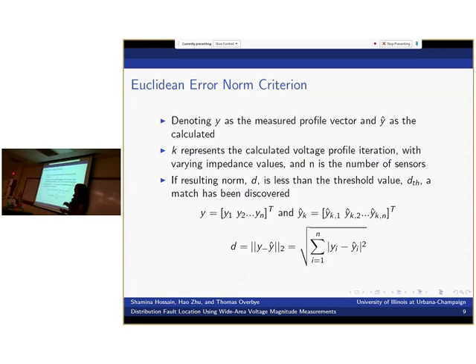And so once we have the measured profile as obtained from the network and a simulated profile for each iteration, we're going to use the Euclidean error norm criterion to compare the two. The error norm value that we get is then checked against a threshold value, which has been derived from the highest measurement error accuracy noise. If the resulting norm is less than that threshold, we deem that we have found the best match and that the fault location and the impedance have been found.